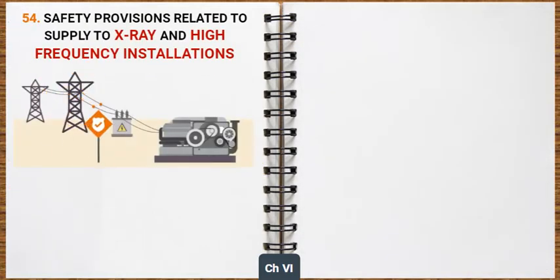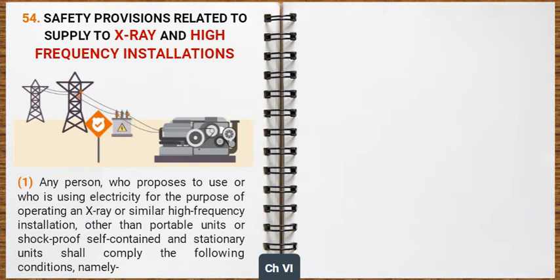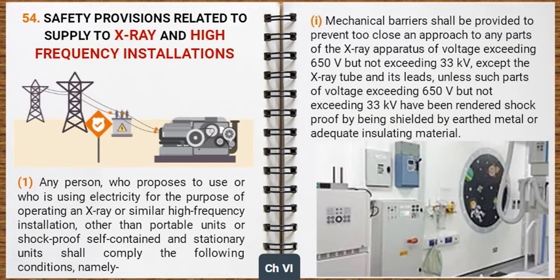Safety provisions related to supply to X-ray and high-frequency installations. Any person who proposes to use or who is using electricity for the purpose of operating an X-ray or similar high-frequency installation, other than portable units or shock-proof, self-contained and stationary units, shall comply with the following conditions, namely, mechanical barriers shall be provided to prevent too close an approach to any parts of the X-ray apparatus of voltage exceeding 650 volt, but not exceeding 33 kV, except the X-ray tube and its leads, unless such parts of voltage exceeding 650 volt but not exceeding 33 kV have been rendered shock-proof by being shielded by earthed metal or adequate insulating material.